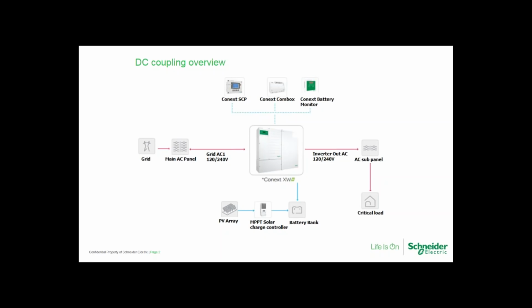So when we talk about reaching the bulk voltage, let's say you have a small battery bank. Let's say you inadvertently didn't consider the size of the bank, and you've got more charge controllers than the battery bank can safely accommodate. And this actually happened in Hawaii not too long ago. There's really no way to program the system to say, hey, let's charge at max charge rate 50% until we reach bulk, and then we'll go ahead and open it up.